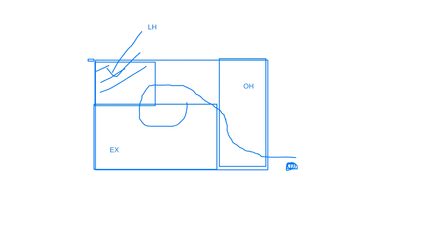For the light hazard, we have 0.10 GPM per square feet. For extra hazard, it might be 0.35 or maybe higher than that. So this area needs more water compared to the light hazard occupancies. In such a condition, we have to do multiple hydraulic calculations. We have to look for the most remote areas and the most demanding areas, and we have to submit the plan accordingly for the fire protection approvals. If we have multiple occupancies like this, we have to go in such a way.